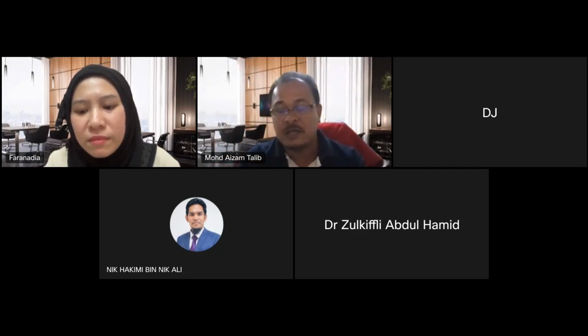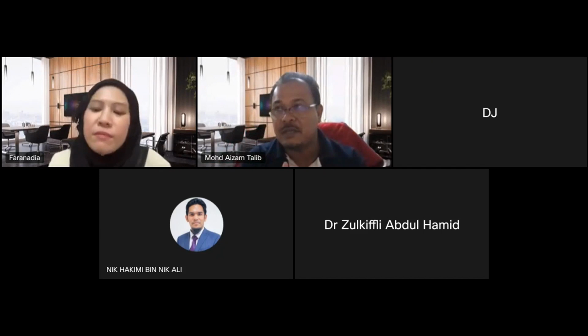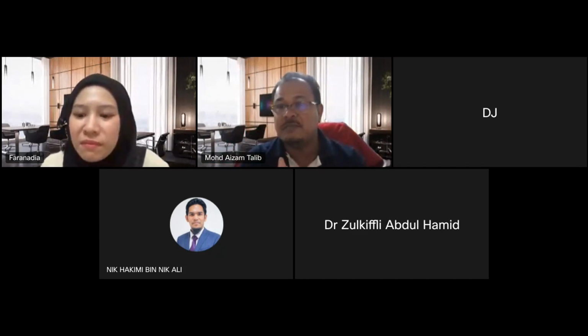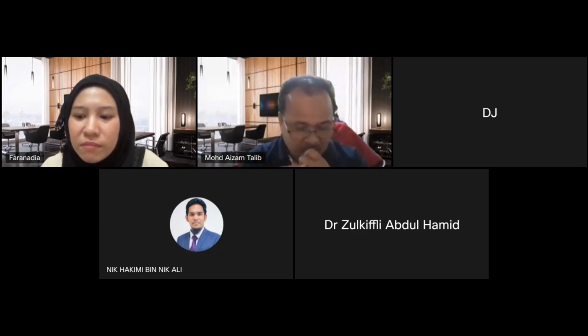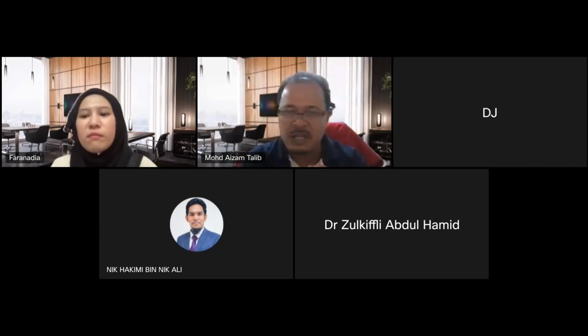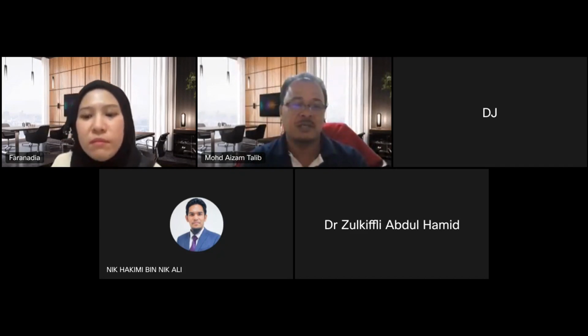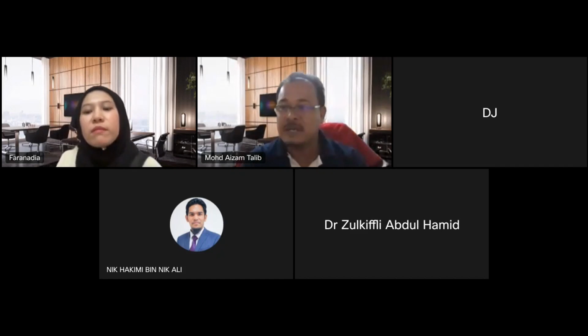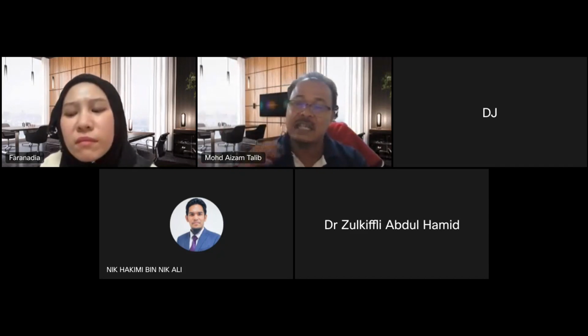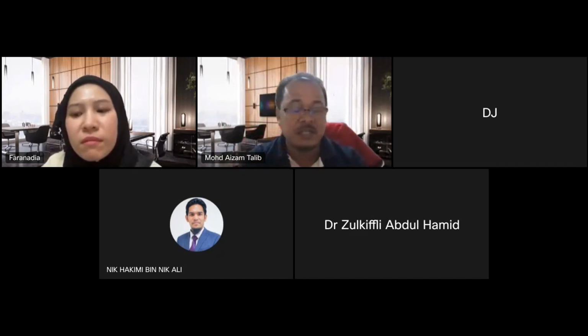for example, a cable in the factory, the PD must be less than 10 picocoulomb. But through our experience, when we test the PD, we usually have at least 1 or 2 picocoulomb. As long as it is less than 10 picocoulomb as required by the standard, then we accept.